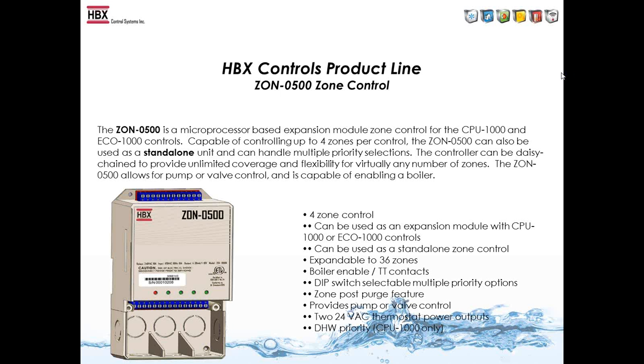It can be expandable up to 36 zones, although that's just an arbitrary number that we thought no one would ever go over. It has boiler TT contacts, so if any of the zones call, there's a TT enable, so you can use it to run a boiler, to run a system pump, or if you're running valves. It has zone post-purge pump or valve control. So 24 VAC power comes out to the thermostats, and you can also have domestic hot water priority. But when you hook this up to the controls, you don't need to cross-wire anything from the zone control to the 1000 control.